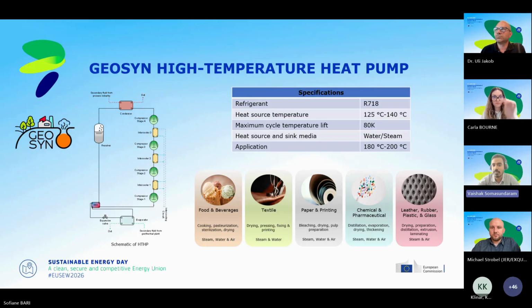The heat pump we are developing is meant to replace this central boiler, not for one specific process. One more thing to add: the working cycle of our heat pump is a vapor compression system, so there is a phase change involved. This heat pump is specifically suited for applications involving steam generation or water to steam conversion.